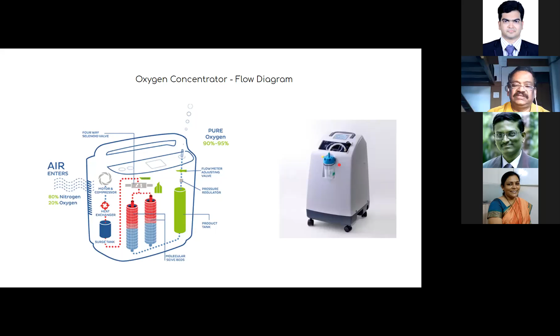Or you can connect an oxygen cylinder instead of an oxygen concentrator. With an oxygen cylinder, you have to have a replacement cylinder when you want to change it. And the oxygen concentrator works on the mains supply, so you have to have a battery backup for the continuous supply of oxygen. Otherwise, if the mains circuit fails, the patient will suffocate.